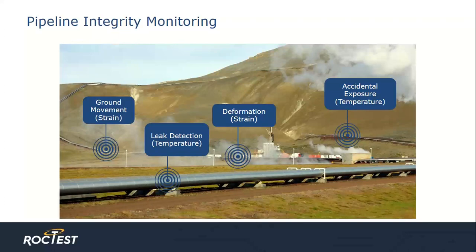Pipeline integrity is another example of long infrastructure monitoring. You can see two different uses of distributed technology here. The first is strain monitoring, as occurs with ground movements adjacent to the pipeline or in a settlement or heave scenario. The other use is temperature monitoring, when monitoring for leaks or in a situation where the pipe has been unearthed, exposing the pipeline to ambient air. In that instance, the temperature change is immediately reflected in the user interface and an alarm would be triggered.